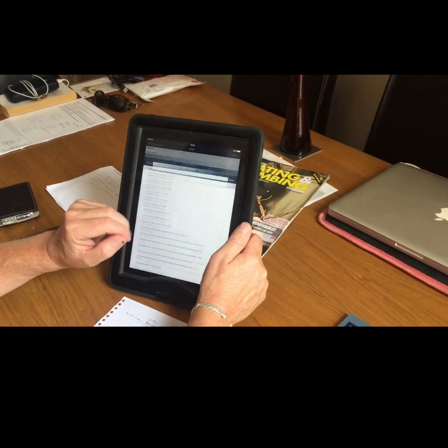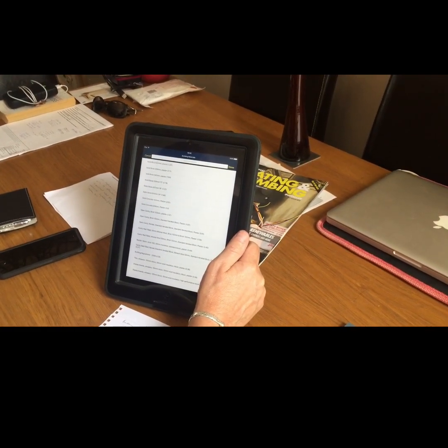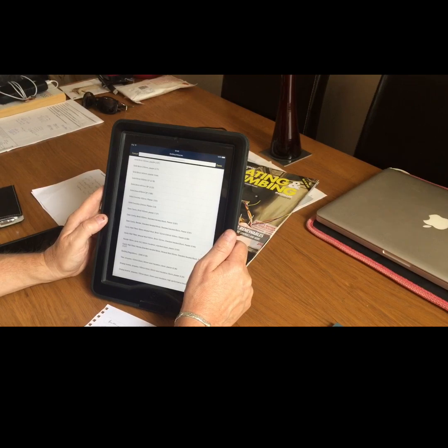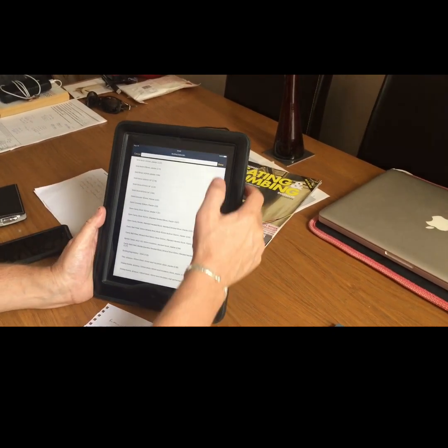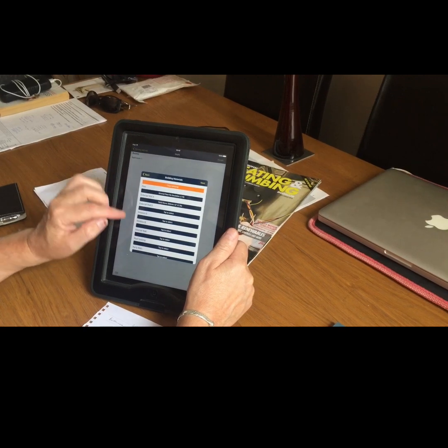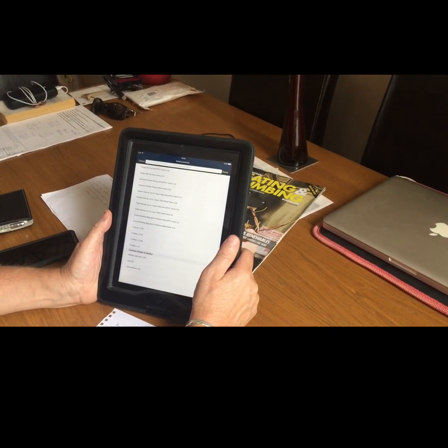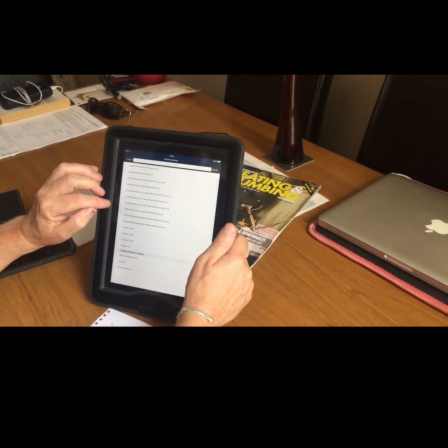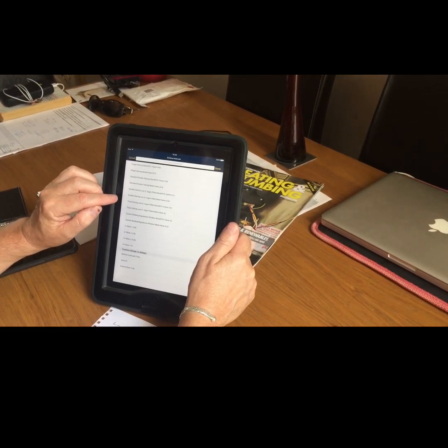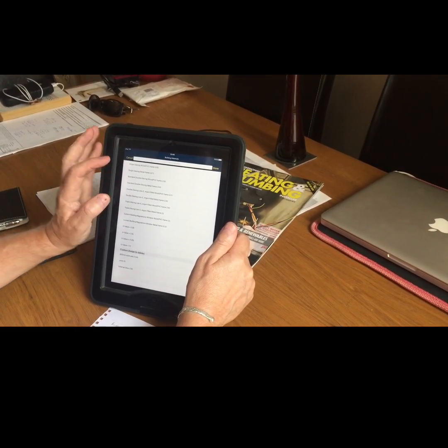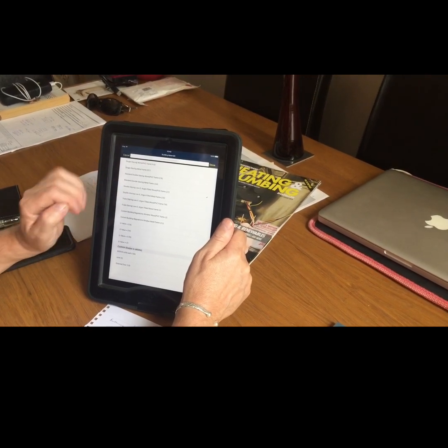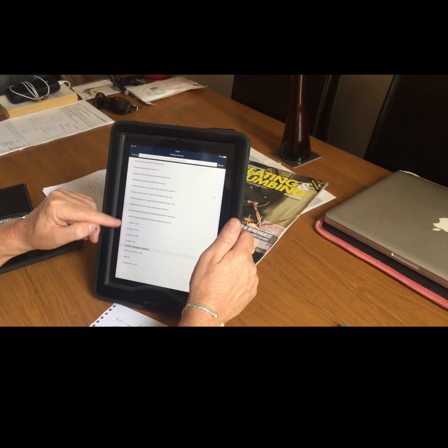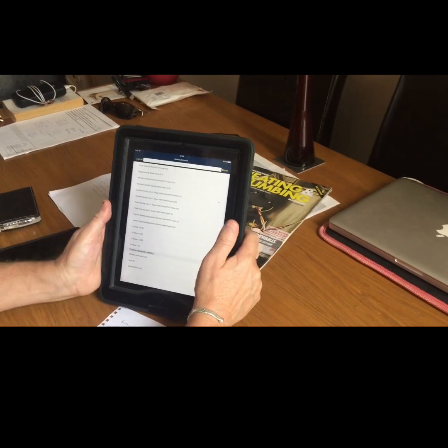So we've got that external wall A. Are we looking at a cavity wall or a solid wall? I'd say it's solid brick. So are we looking at a 300mm solid brickwork, I should think? Standard, okay. So 2.78. Next to it, the window type, what have we got? Double glazed, single glazed? Double glazed. Timber? PVC. Double glazed, PVC. Okay, that's going to be 2.1. And again, we can add custom values, or if you know the U value of the product, you can click on one of these, which covers most windows that are on the market.